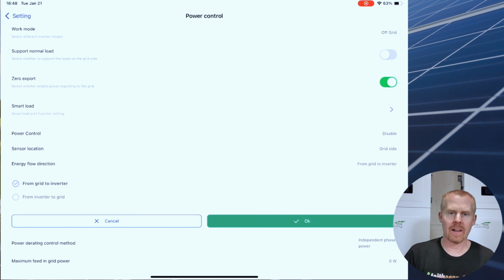Energy flow direction. So the CT clamps that come with the inverter have to be clipped on with the little arrows pointing a certain direction. And if you accidentally clip them backwards, you can come in here to energy flow direction and switch the direction. It only works though if both clamps are facing the same direction. If you've got one facing the inverter and one facing the grid, it's not going to help you. They both have to be facing the same direction, but this option here allows you to use the software of the inverter to switch that direction so that it can track power flow properly.